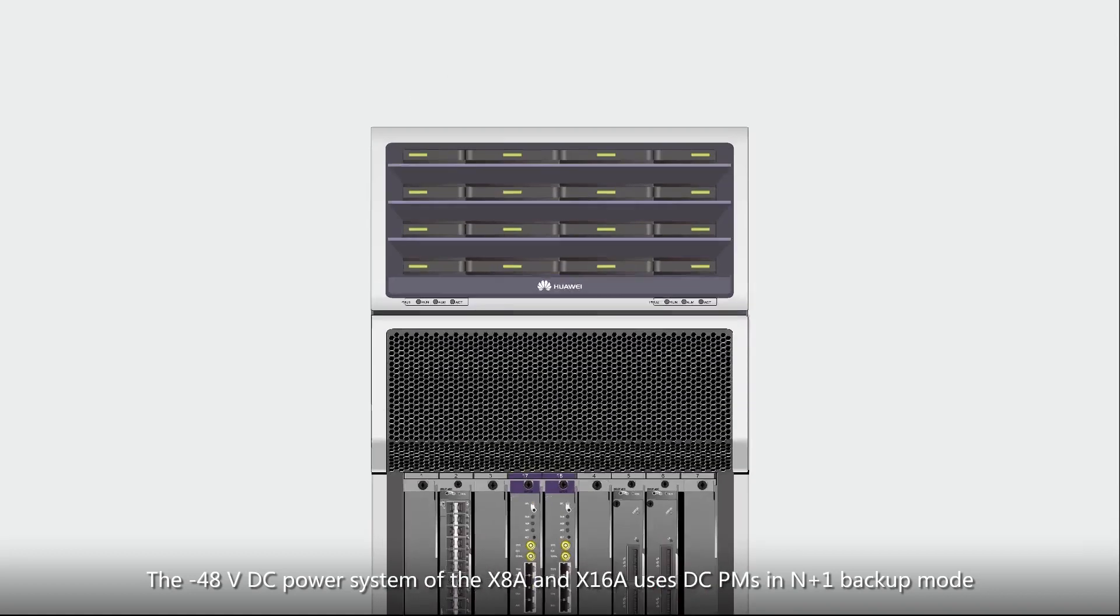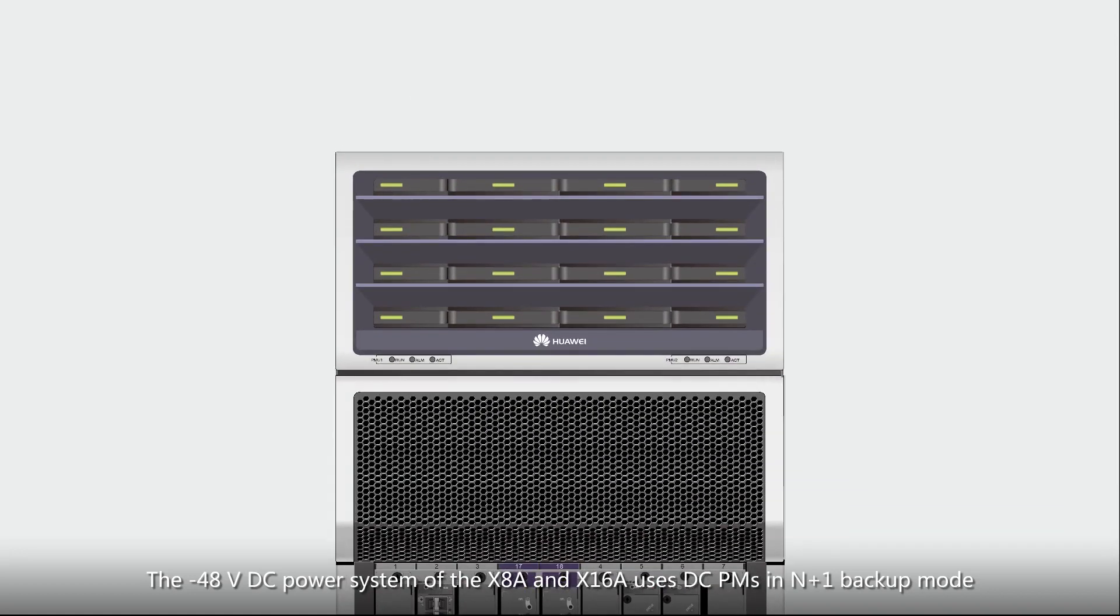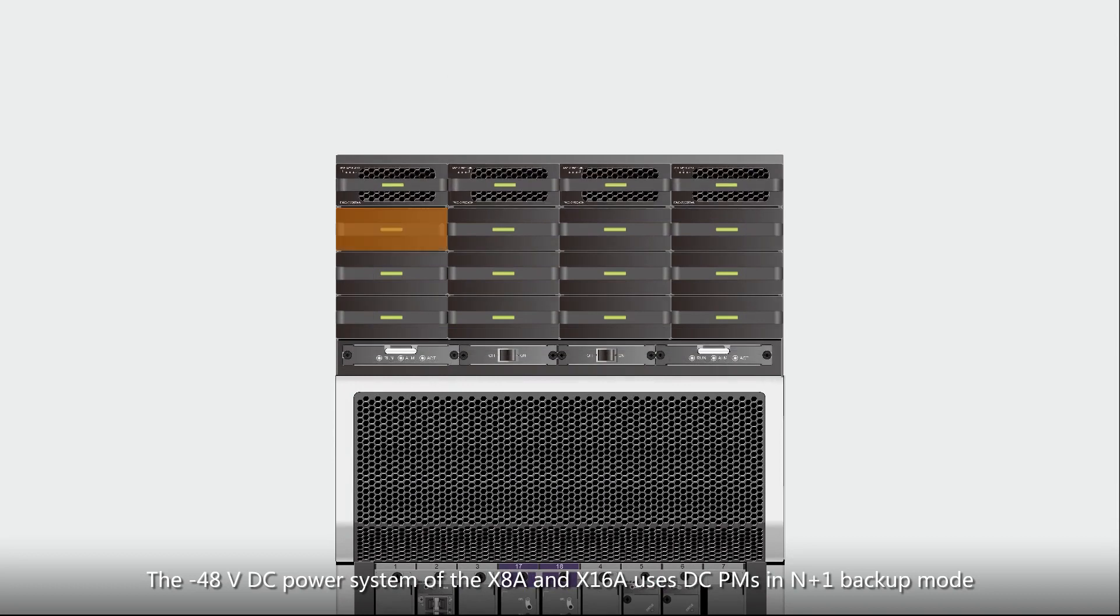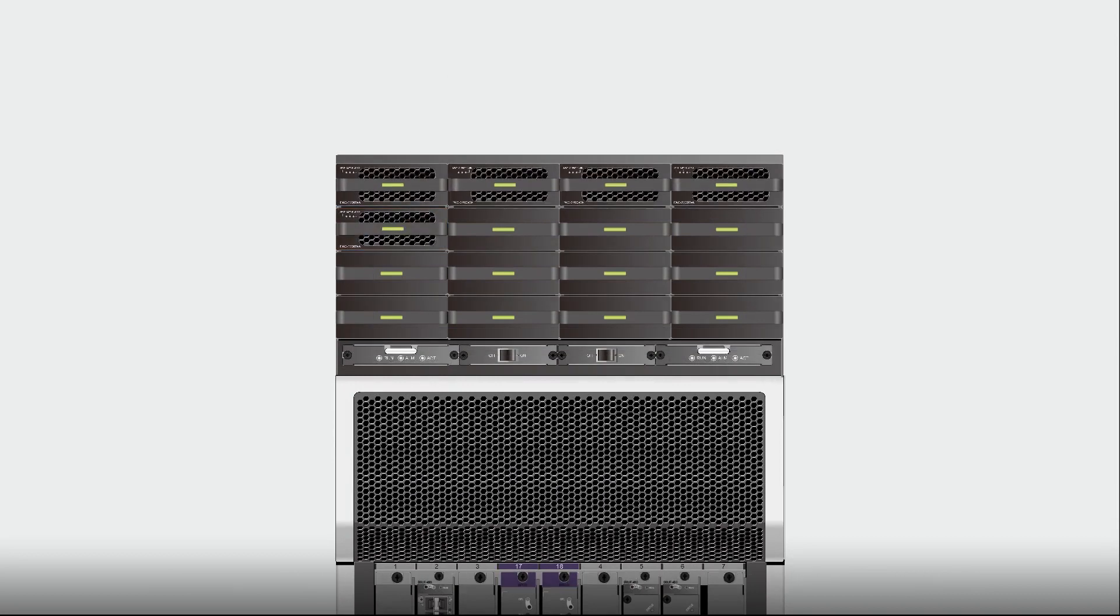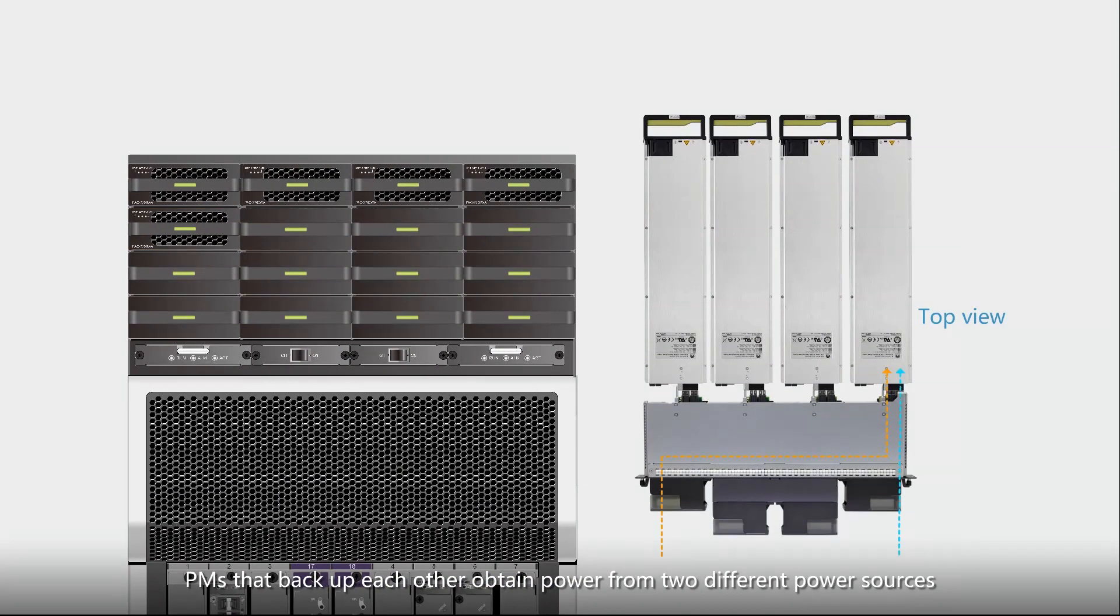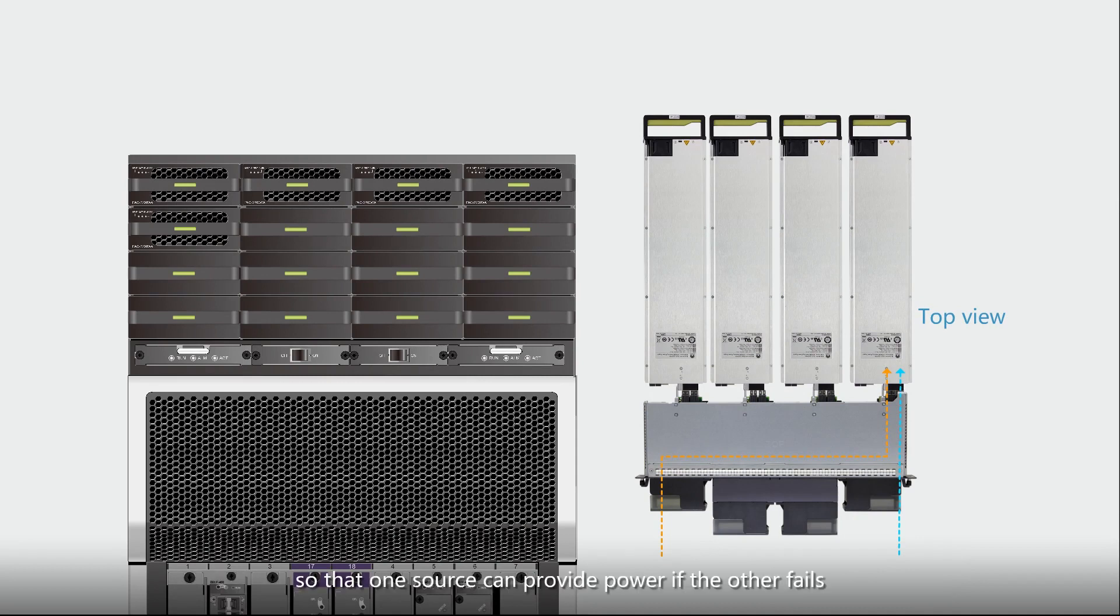The negative 48V DC power system of the X8A and X16A uses DC PMs in N plus 1 backup mode. PMs that backup each other obtain power from two different power sources so that one source can provide power if the other fails.